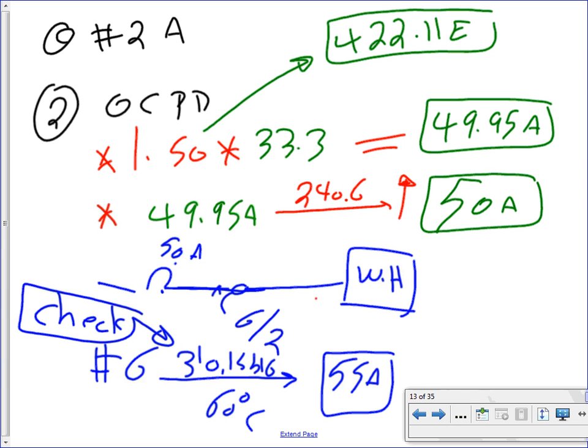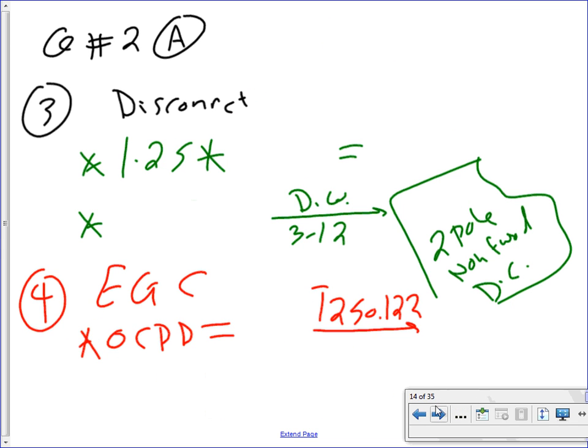That will give you a number under the 60-degree column. 40. So that will give you 40. Then can I put 50 amp on it? No. So this is the check. Did you guys see that on the bottom, the check? We're good. In this case, 6-2 is good. That's my overcurrent protection device.